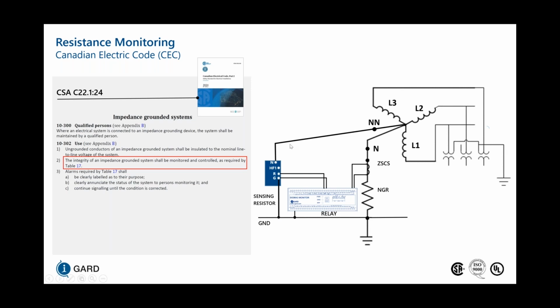So the idea is that from the relay, a high frequency signal gets injected into the sensing resistor, which takes the path up to the XO point and down through the resistor. The reason why we adjusted from a DC to a high frequency AC is because when we were reaching the XO point with the DC based signal, it was realized that a lot of the signal is leaking out into the system if you have YY connected PTs where the primary is grounded. So because the DC signal sees these inductances as short circuits due to XL equals 2 pi FL, the signal can leak out and create a false realization that they've checked the NGR when they haven't really checked the NGR.